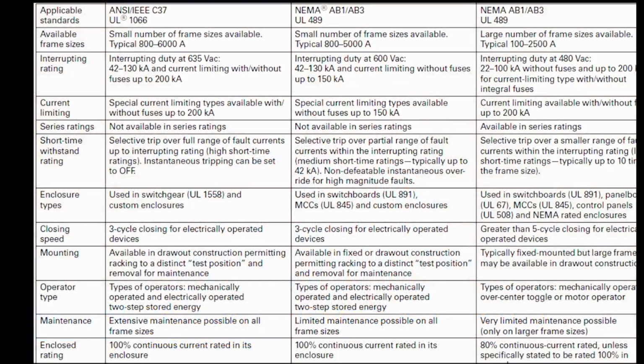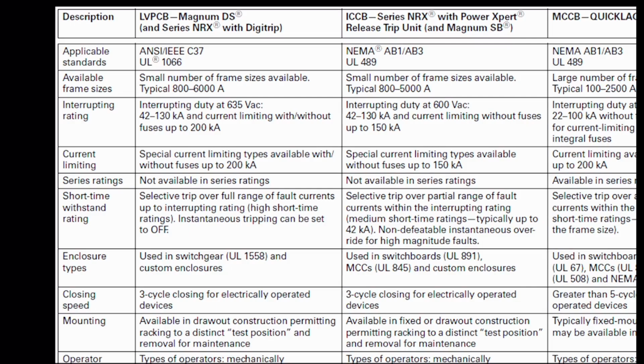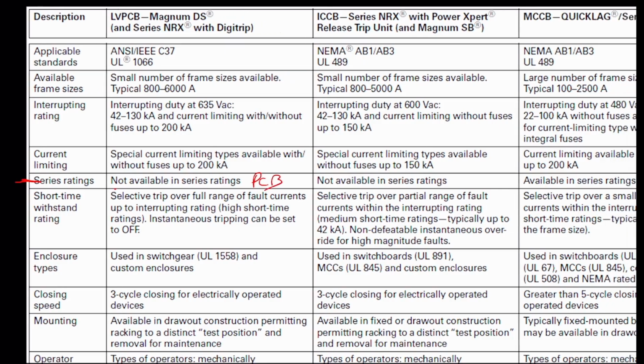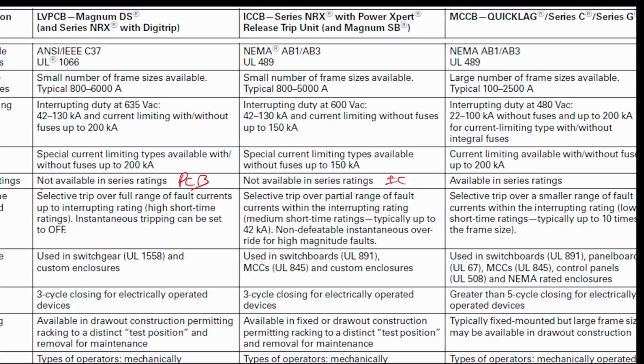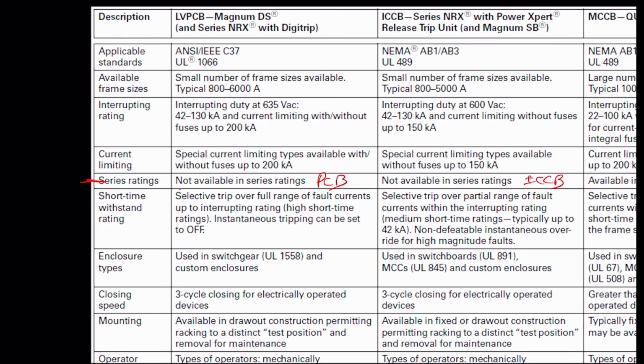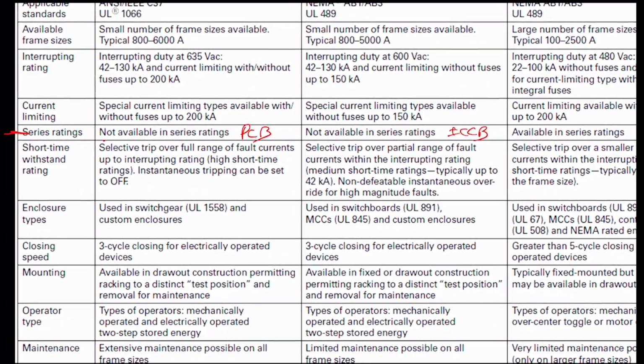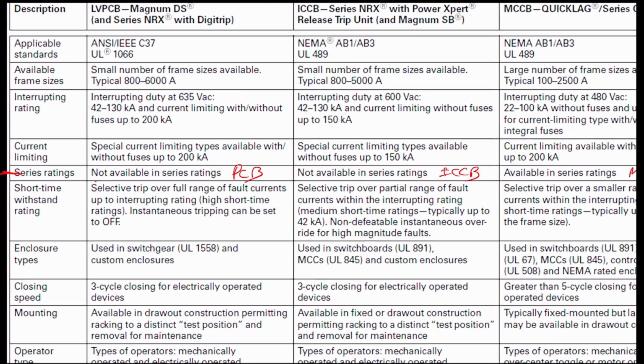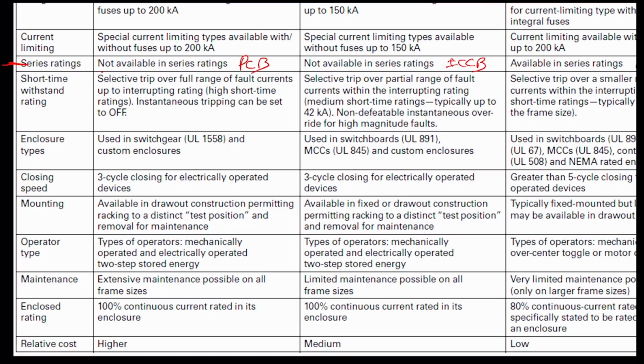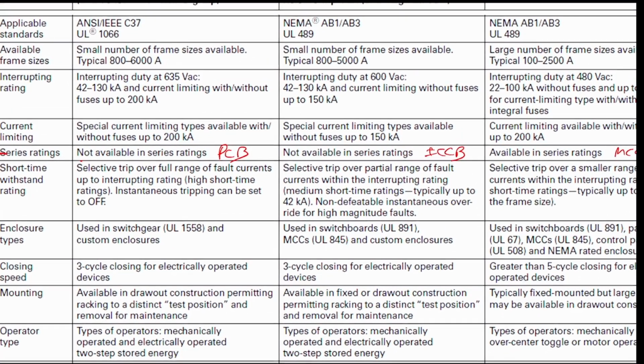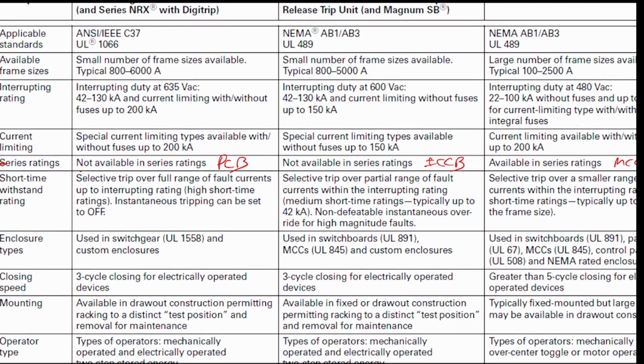some of the really pertinent information. Now here's some more information. Okay, here's a few more little tidbits of information. Series ratings are not available in the power circuit breaker, not available for the insulated case circuit breaker, and it is available for the MCCB. That's your series ratings. You have a short time withstand, instantaneous. Where's the instantaneous? Enclosures, maintenance, enclosed ratings, relatively cost. I don't have an instantaneous. I have an interrupting rating.